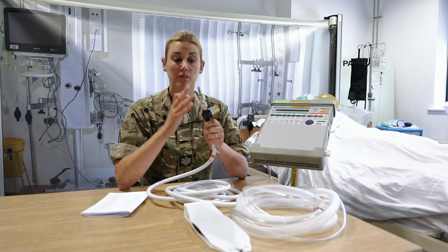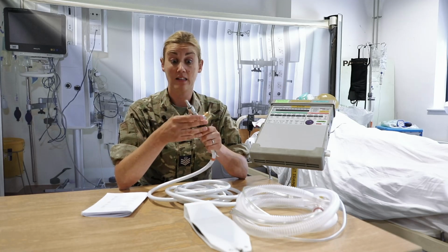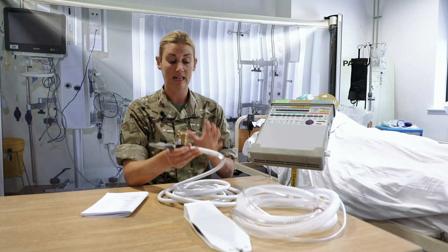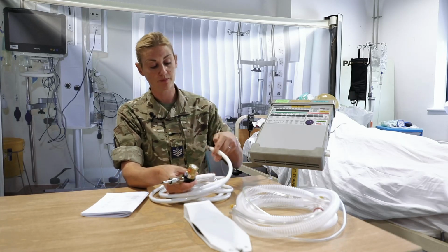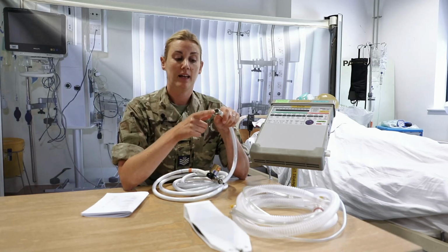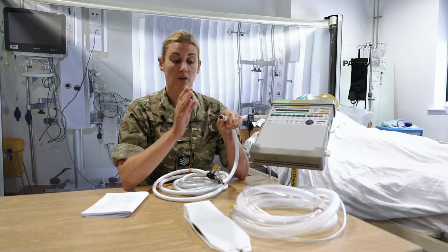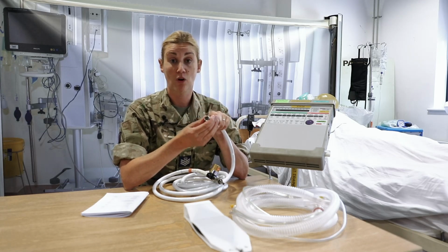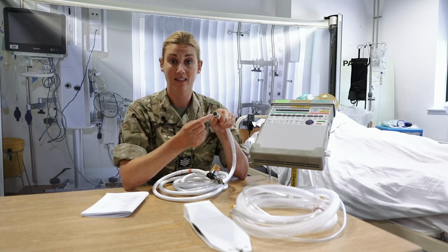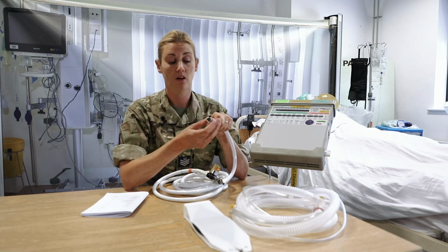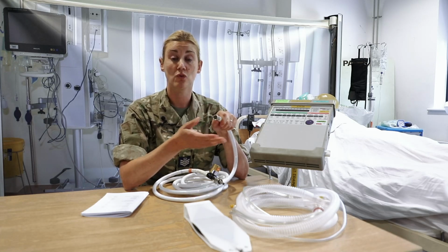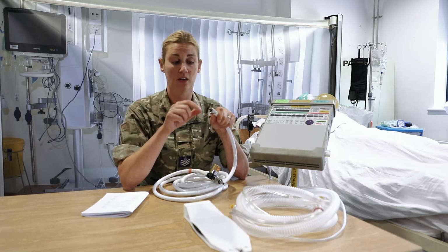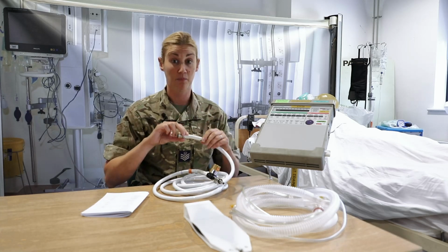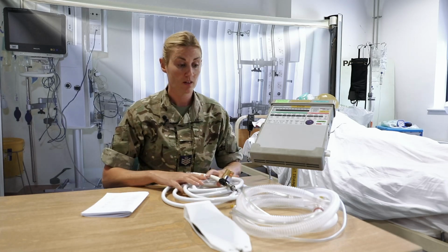Check your Schrader valve, make sure that there isn't, again, any dirt or dust or particularly grease, anything that's going to cause a fire hazard. And then, as per the orientation video, have a good look at that rubber washer, that Bodok seal on the inside of the oxygen hosing itself. Make sure there aren't any teeth cut out of it or anything that's going to make you have a big leak in oxygen.